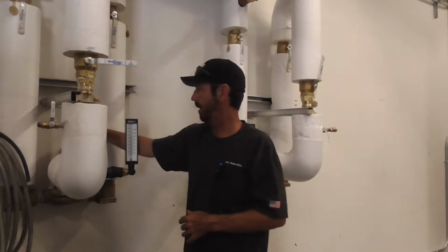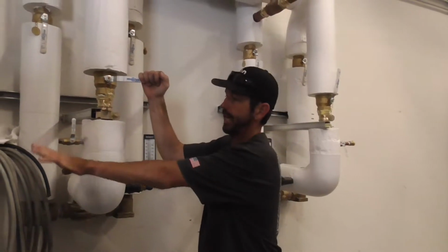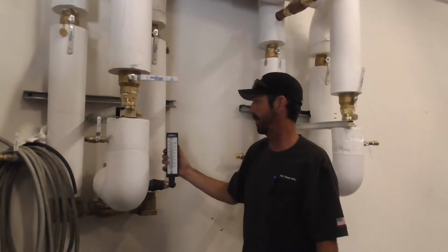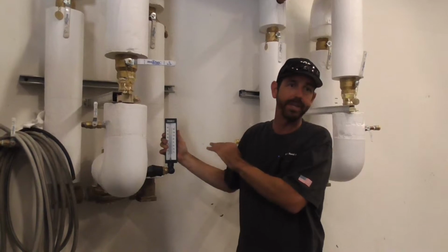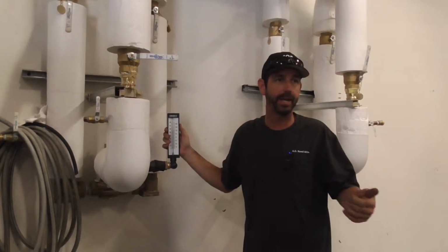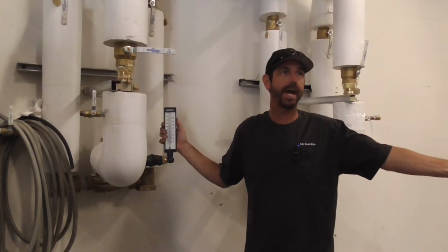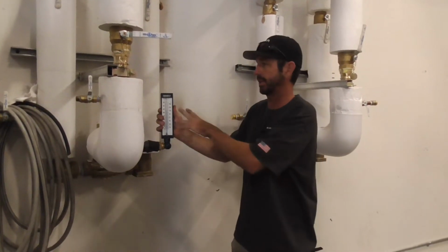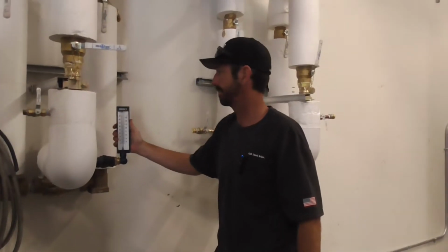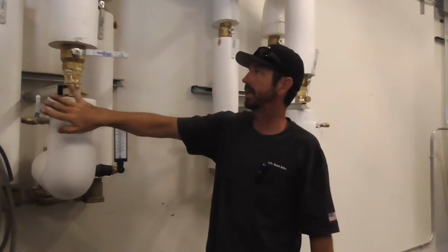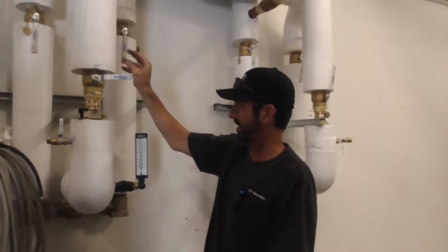Okay. So again, the valve's off. We're checking water to the drain. We can check our set point. At that point, you can still verify the calibration of your thermometer too with the handheld that you know is accurate. You know, you can measure that at the water source too to make sure that your thermometer is good. Okay. Once we're done, we'd close the valve and we can open this back up for service.